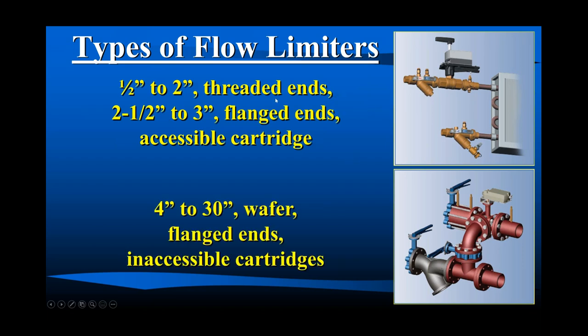I would say 98% of the flow limiters are in this size because, again, they only go with the terminal. Do we have larger ones? Yeah, we do. We have the 30-inch for campus stuff, if that's part of what you do. But if you have a real large air handler, yeah, it would look like this. There's the automatic flow balancing valve right there. Same as this, right? Here's our butterfly valve isolation, strainer. There's a three-way valve setup, bypass, and here's our terminal unit. Come back out, air vent. There's our three-way valve, and there is our automatic flow balancing valve, verification ports, and lastly, butterfly isolation valve, true isolation valve.